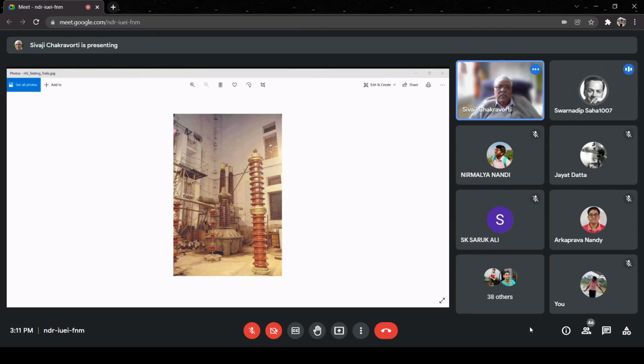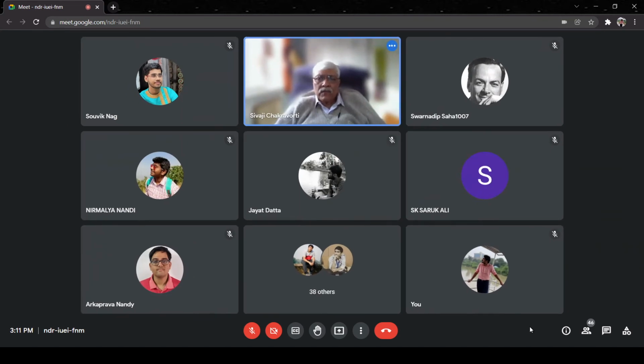Yes, sir. See, this is our high voltage lab. If you can see my mouse moving, this one here is the 250 kV testing transformer. By the way, testing transformers are always single phase, because you don't require three phase for testing. That is not required. So you can see this is actually a real life testing transformer. So this is what we are going to discuss.